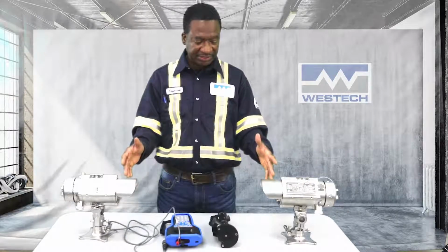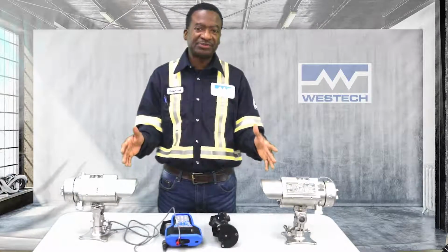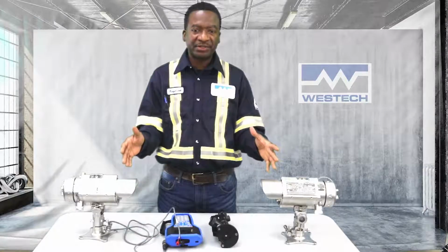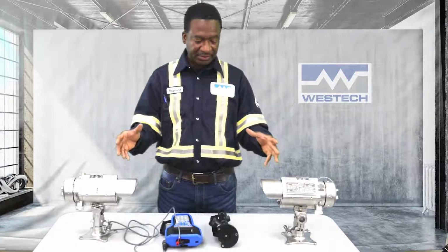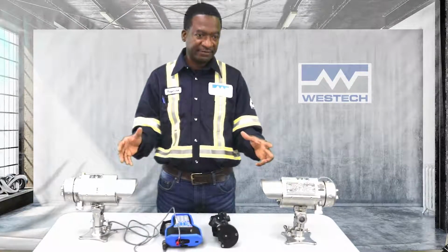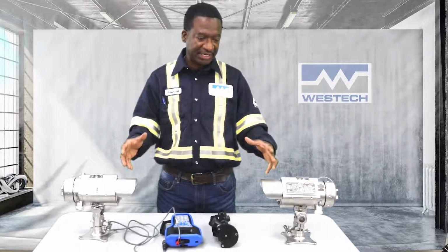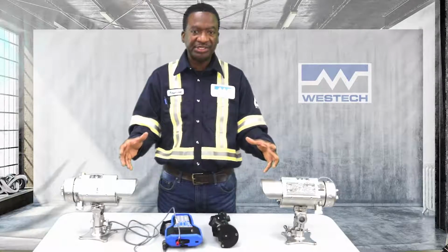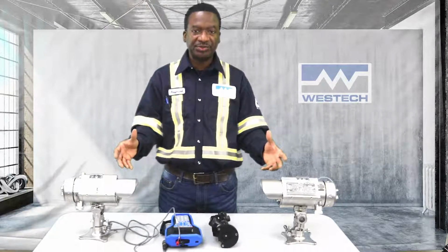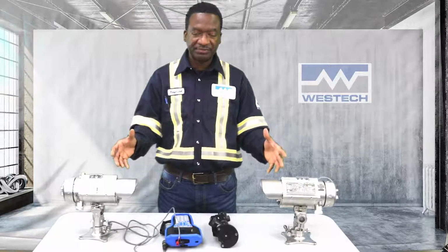What this simply means is that the system obeys what you call the Beer-Lambert law, and gases will absorb infrared as well as UV energy, and that energy is compared to a reference wavelength, which remains unchanged, and then that is in direct correlation to the gas concentration.